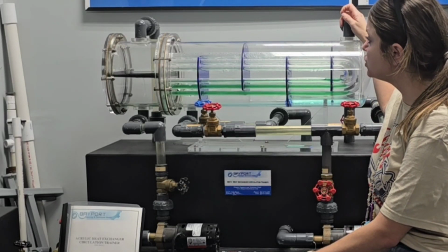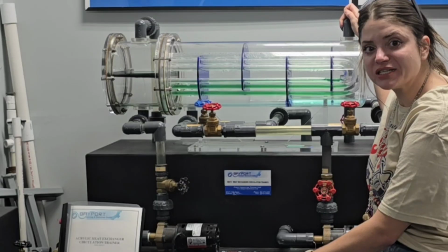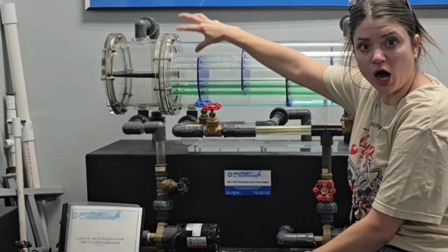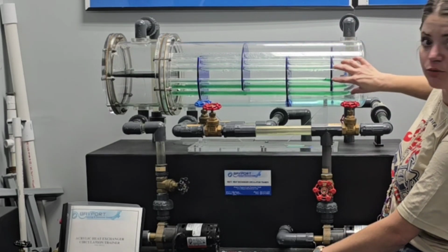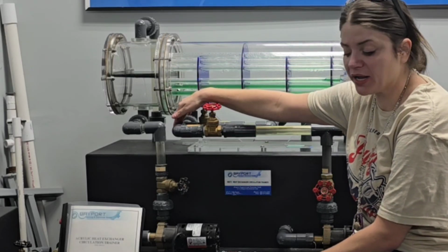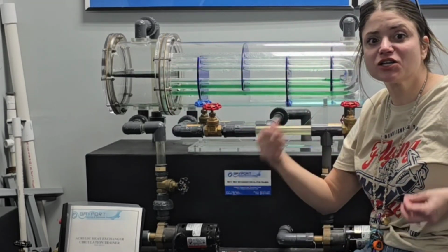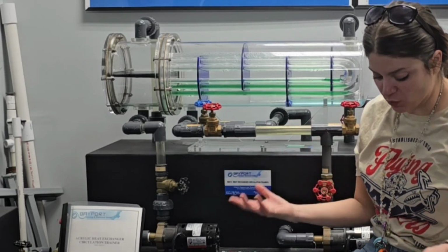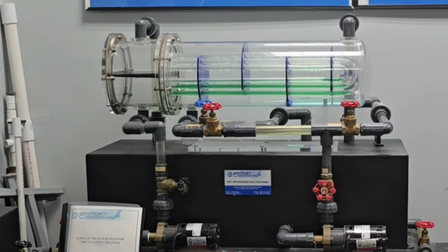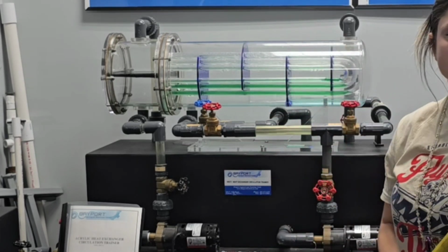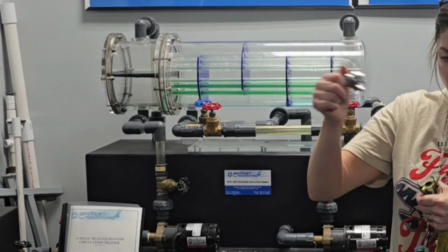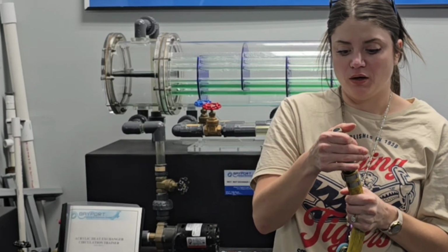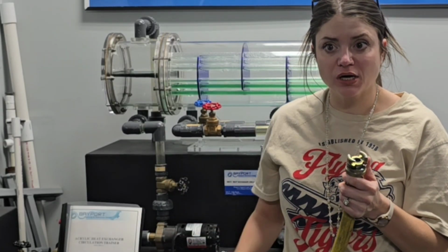So what we could do is use nitrogen or steam to fill up the top of the tubes, fill all this up, and then it will push it out to the low point, okay? Because this is just an illustration of a shell and tube exchanger, it doesn't have bleeders on it, but what we would do is use fittings. See the fitting on there? We would use fittings to connect to the end of a bleeder valve, connect the hose, and connect the other end to our utility station.